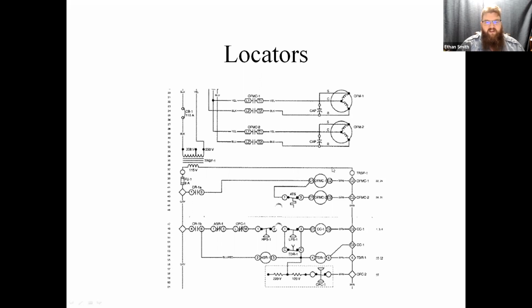Let's focus on this bottom part for now. We've got our transformer here. It converts 208 or 230 volts into 115 volts. We've got our neutral down one side and our power down the other side. We've got this fuse, which gives us our fuse designator and our amperage rating. Let's say we were trying to figure out why my compressor is not coming on, my first stage compressor. We come down here and we've got this first branch, which says CR1A. This tells me this is my control relay 1A, and it's got a normally open set of contacts.